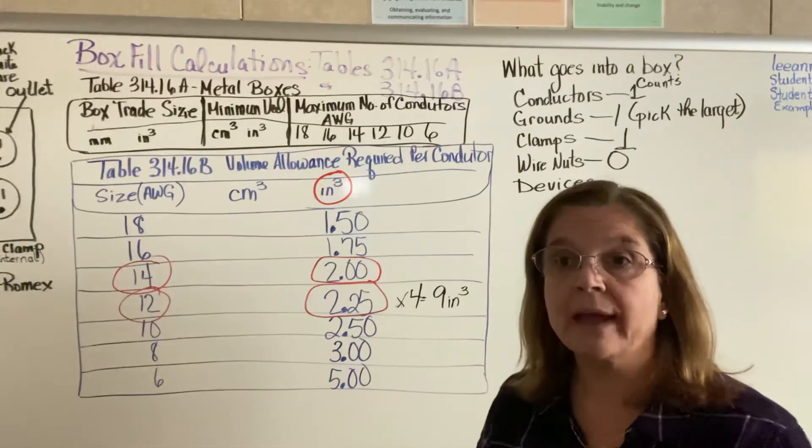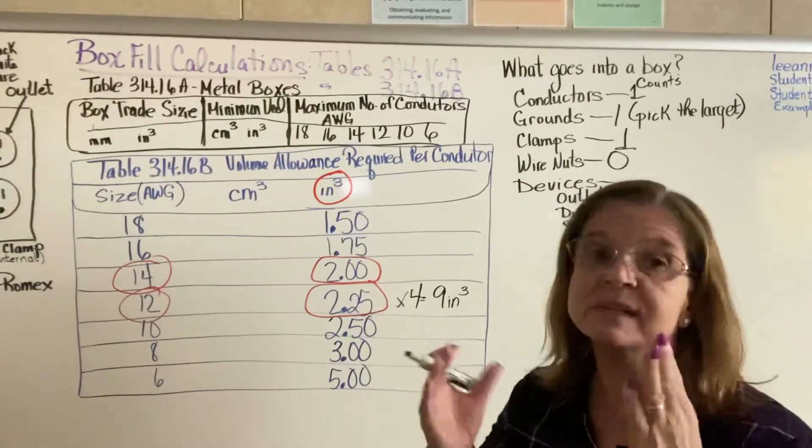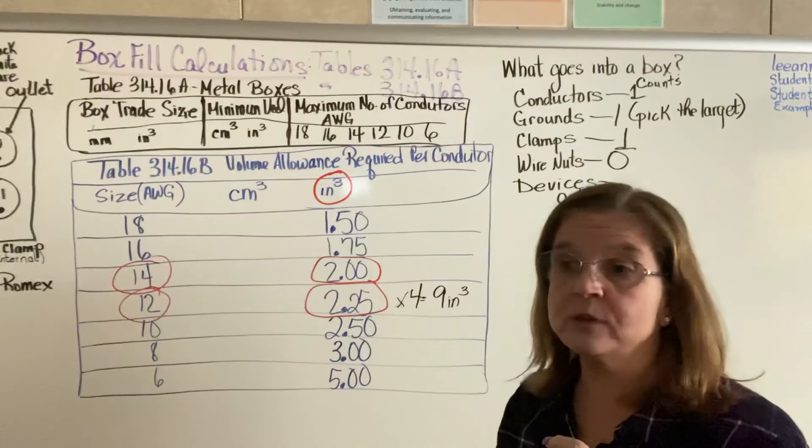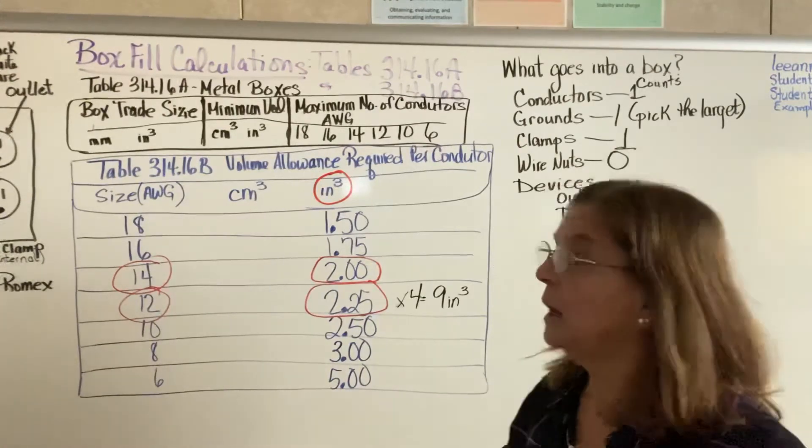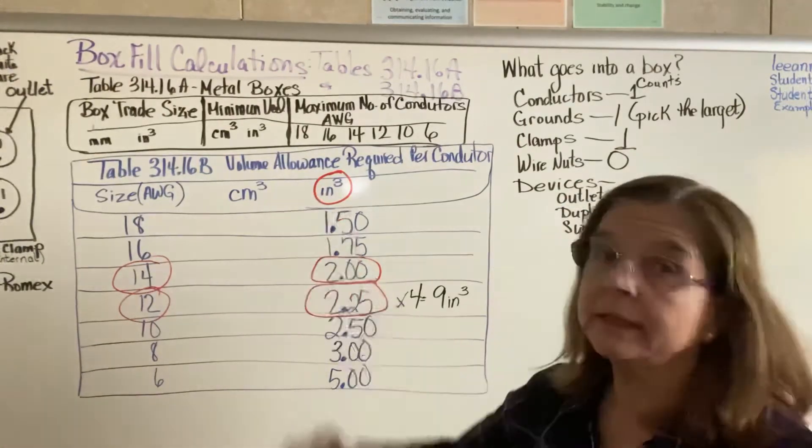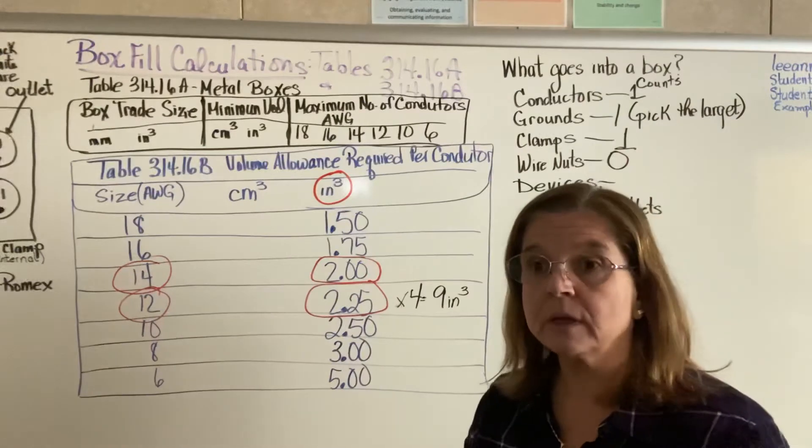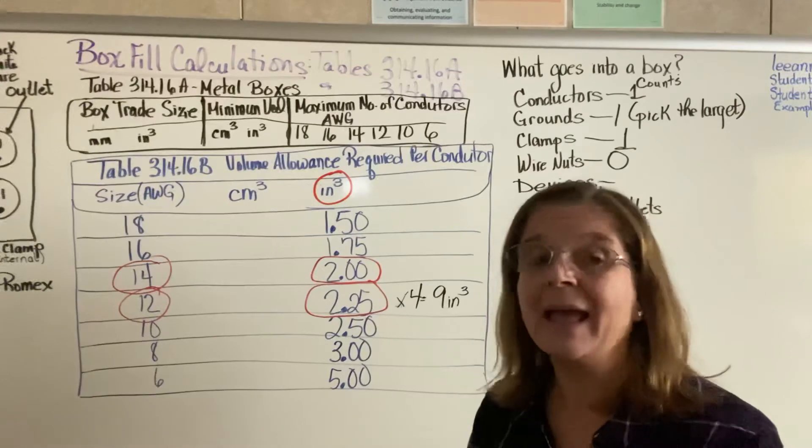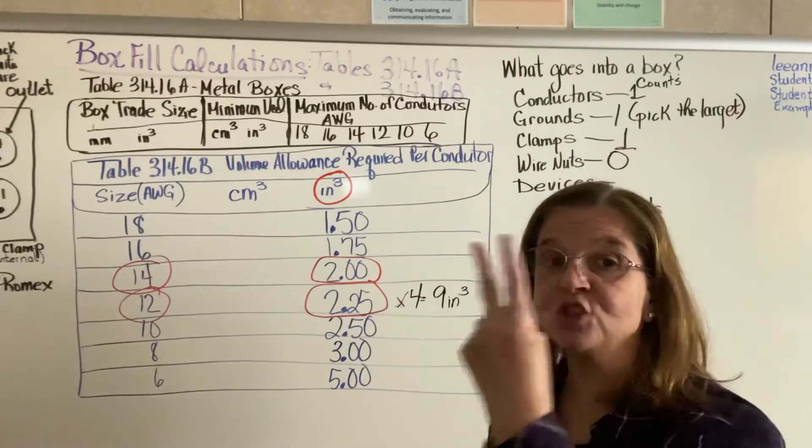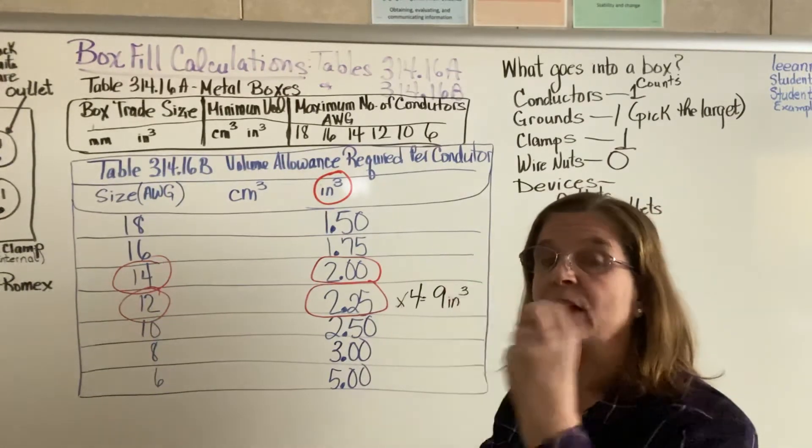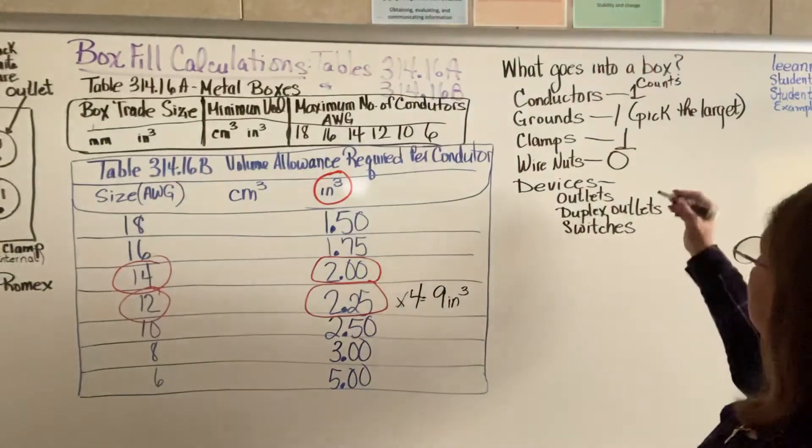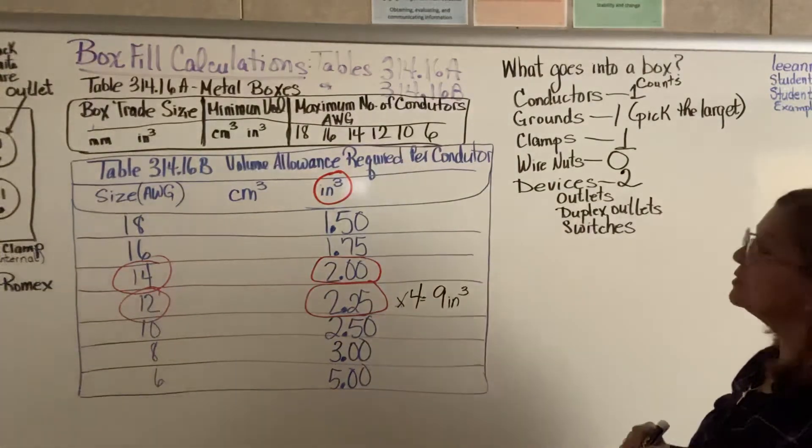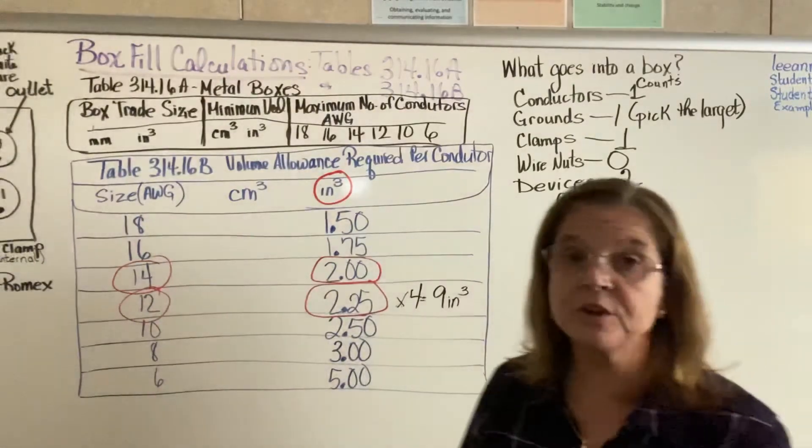And the last thing that you have is the actual device. You have this box. What are you using it for? Are you going to use it to install a switch, an outlet, a duplex? Whatever device you are going to put in that box, every device counts as two. So that's a typical box, what you would have inside.